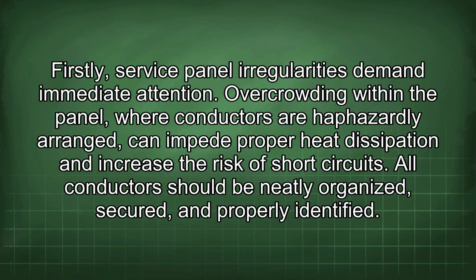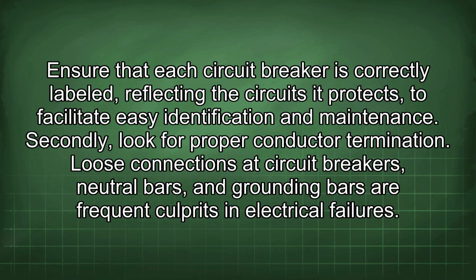Firstly, service panel irregularities demand immediate attention. Overcrowding within the panel, where conductors are haphazardly arranged, can impede proper heat dissipation and increase the risk of short circuits. All conductors should be neatly organized, secured, and properly identified. Ensure that each circuit breaker is correctly labeled, reflecting the circuits it protects to facilitate easy identification and maintenance.